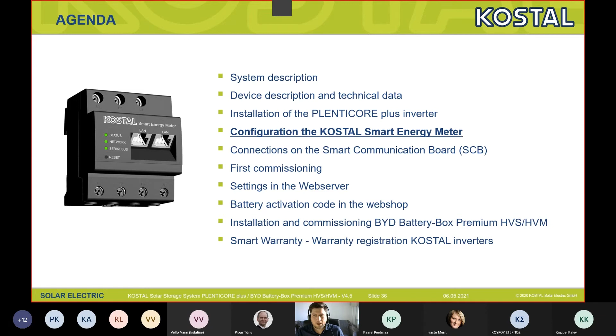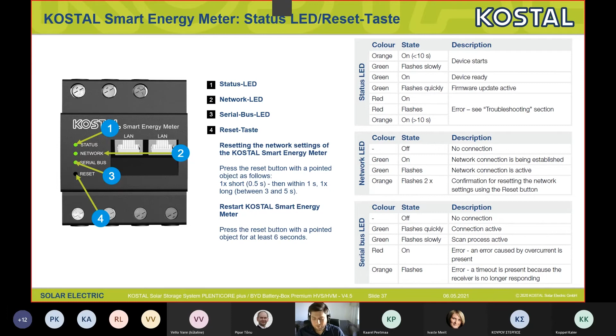Also, let's say some words about the Smart Energy Meter. It looks like the photo that you see right here. There are some status LEDs. Number 1, the number 2 is the network LED, and the number 3 is the serial bus LED. And also there is a small reset tactile switch inside there. According to the situation, if it is flashing green or red or orange, there are relevant descriptions: whether the device is ready to use, or if the firmware needs to be updated, or if there is a connection with the inverter, or if there is no connection. And the most important thing is that the smart meter is already pre-configured. You don't need to make any settings to this meter. You only have to connect the serial bus connection, the Modbus connection.